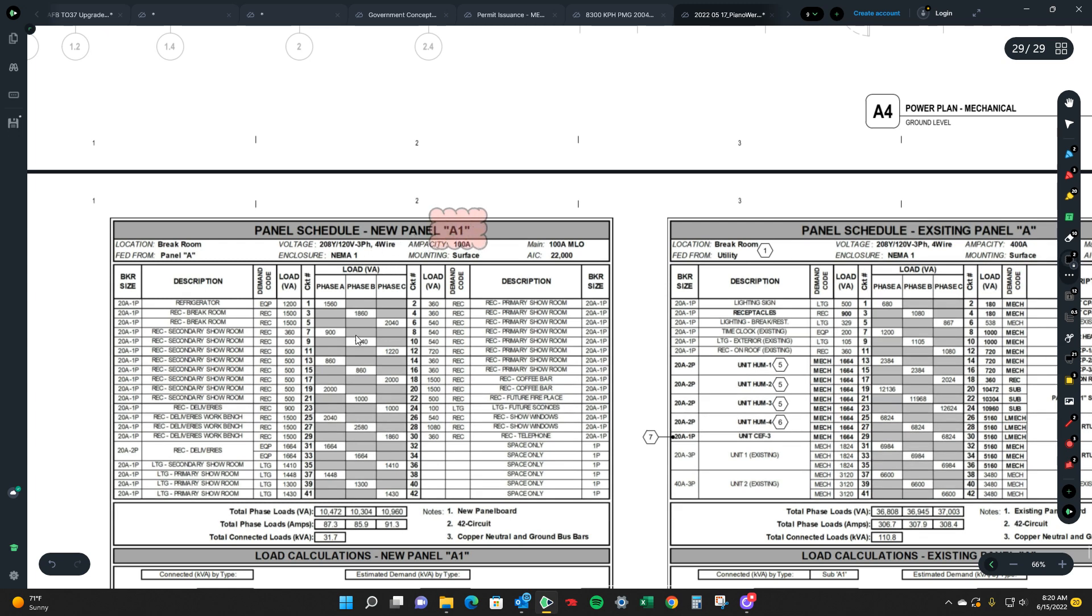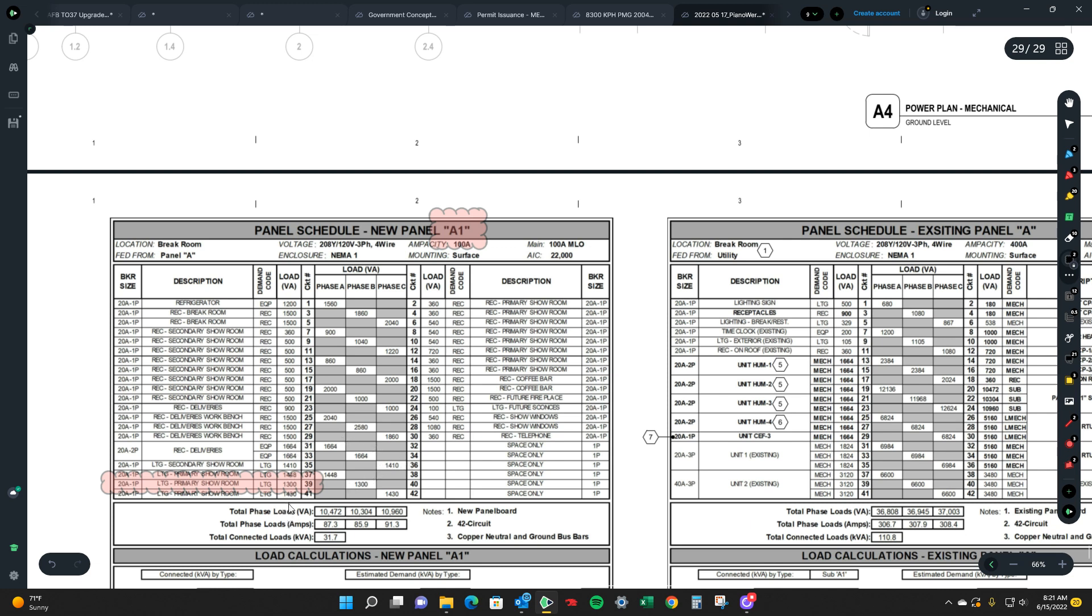And then that's going to tell you you're going to use a 20 amp circuit which means you're going to be using number 12s for that lighting circuit. This will tell you the estimated load and demand of that, like what it's for.